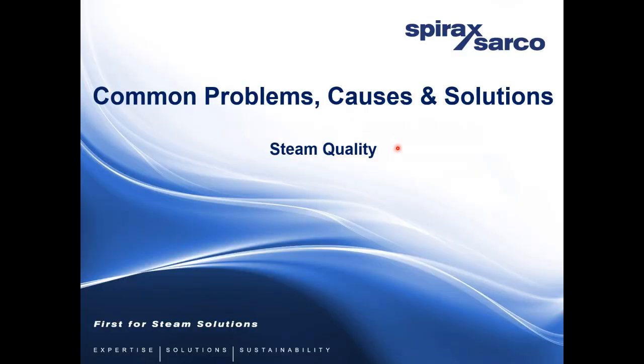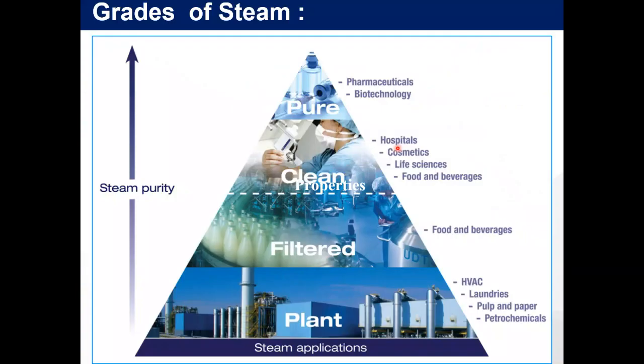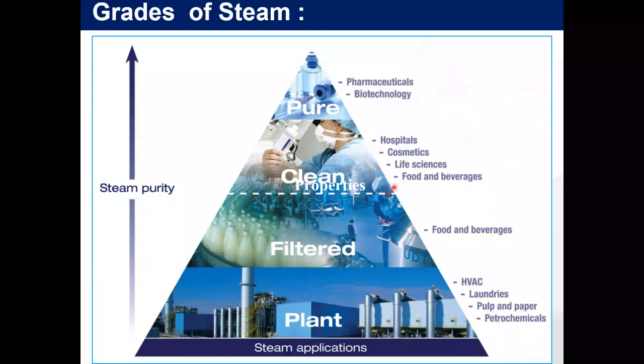So common problems and causes for steam quality. We have many different grades of steam, and what you use depends on your process. So plant steam, normal steam coming through filters, just your normal strainers. These are used for, as it says, HVAC, laundries, pulp and paper, petrochemicals. The food and beverage industry will use filtered steam.